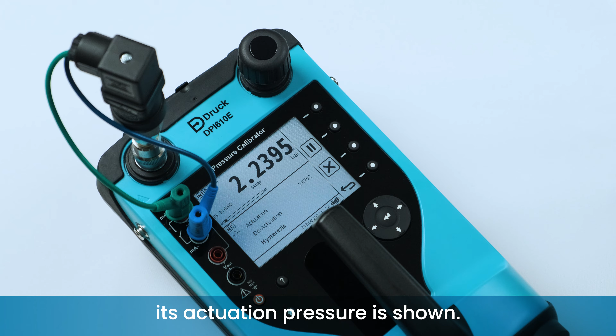Now we start to decrease the pressure to its expected reset point. The switch is configured to reset at 1.9 bar. When the reset pressure is reached, the switch deactivates and the pressure is recorded. The test is concluded with the hysteresis value calculated and displayed.